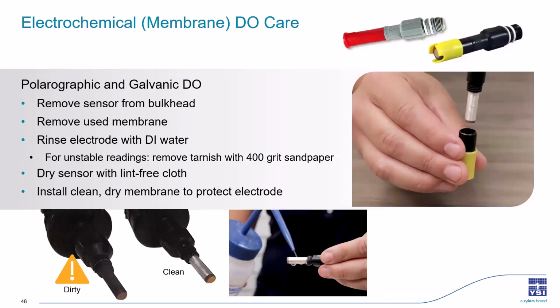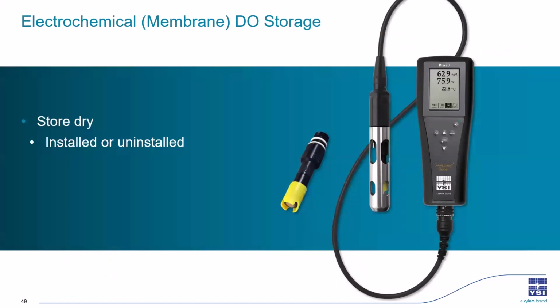And then go ahead and dry it with a lint-free cloth and install a new dry cap without the electrolyte solution to protect the electrode. Then you'll just go ahead and store it dry. If you do end up filling the cap with the electrolyte solution and leave it for a long time, it could leak out over time and your sensor tip could be covered in little crystals. That's not a big deal, but you'll need to just clean it again when you take it back out. And if you have a multi-sensor instrument, the DO sensor can also be left installed as long as the other wet storage sensors have been removed.